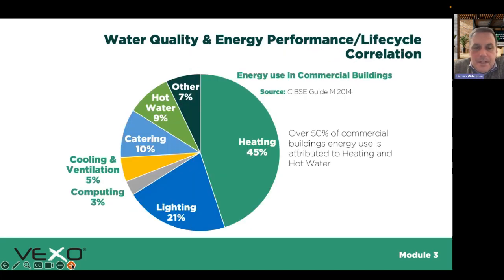Other areas, we've been working with Loughborough University, supporting a PhD, and we've seen significant savings by cleaning up existing systems. When you consider the amount of energy used in a commercial building, and I need to update this, I do apologise, because now there is a CIBSE Guide M that's come out this year, there's been an update to it. But essentially we're using a huge amount of energy in a commercial building associated with heating and the hot water. Unless you've got direct fired cylinders, even the hot water is coming off your core heating system. So if that water quality is not right, you can be significantly impacting the efficiency of that system, potentially by up to 20%.